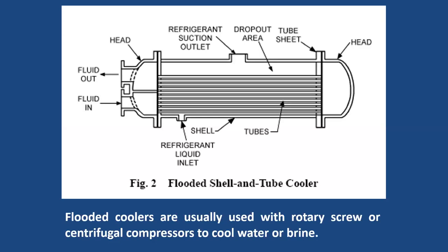And again, flooded evaporators are generally recommended if the cost of the refrigerant is low. For costlier refrigerant, flooded evaporators are generally not recommended because they increase the initial cost. Here the initial cost is substantially high for a flooded evaporator because of the refrigerant cost. But as far as the running cost is concerned, flooded evaporators are more efficient than the DX type evaporator.